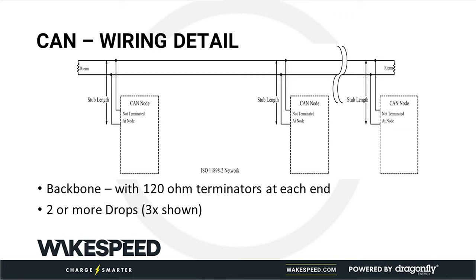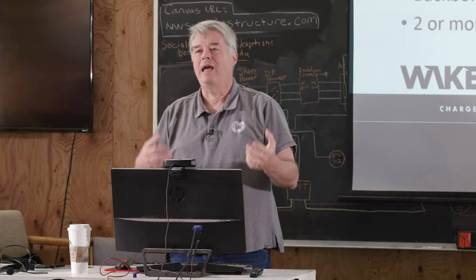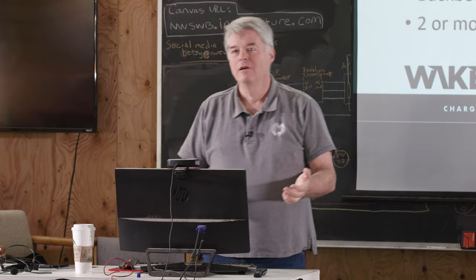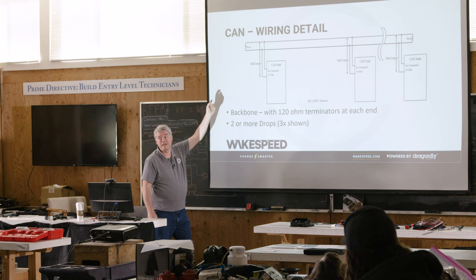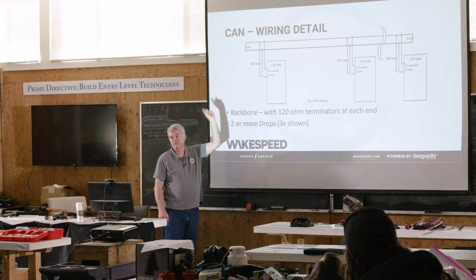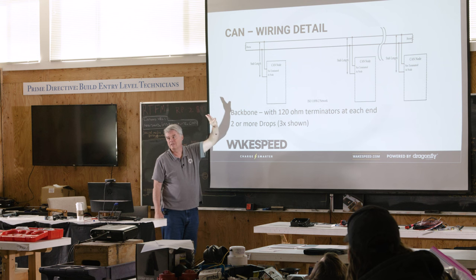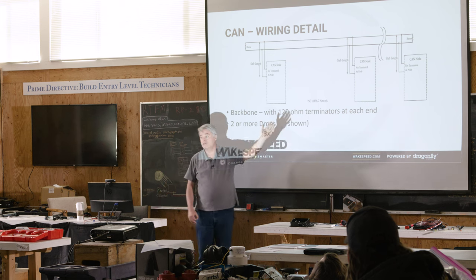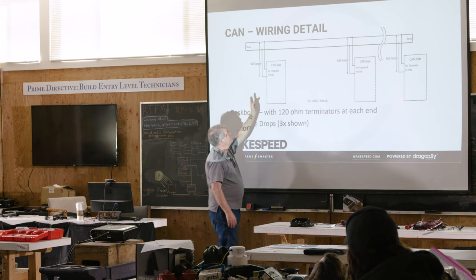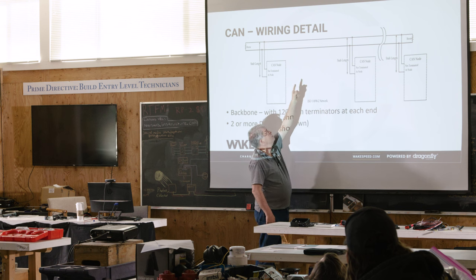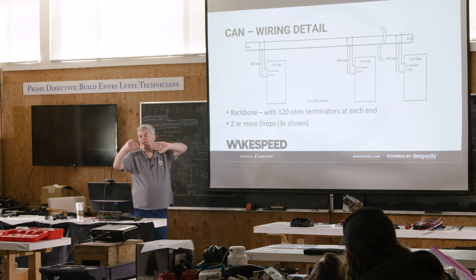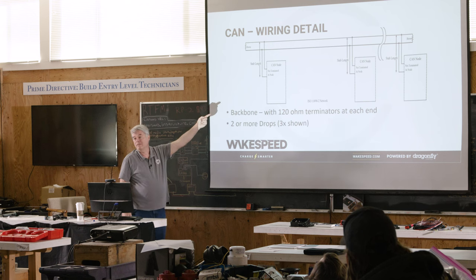At the end of the backbone there is a terminator on each end — 120 ohms on each end. This is a hardware signal transmission bus, and the energy has to be terminated or it'll be reflected and you'll get nulls. If you don't absorb the energy when it gets to the end with the terminator, it will be reflected due to the impedance mismatch, inverted 180 degrees. The original signal and the reflected signal cancel each other out — 10 minus 10 equals zero. That's called a null.